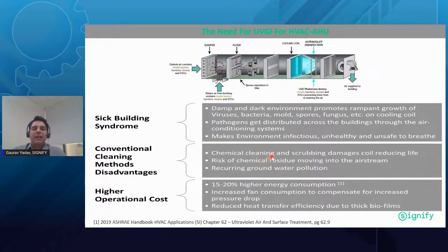And those chemicals can further come into the indoor environment with the air, and that will further contaminate the indoor air quality. And they can also be responsible for groundwater pollution because those chemicals can seep into the groundwater. And this chemical cleaning and mechanical cleaning method you can do only periodically. It is not like day in, day out you can clean the cooling coil. You can perform that cleaning within 15 days or within 1 month of time. So within that period of time, the infected air keeps coming into the indoor environment.